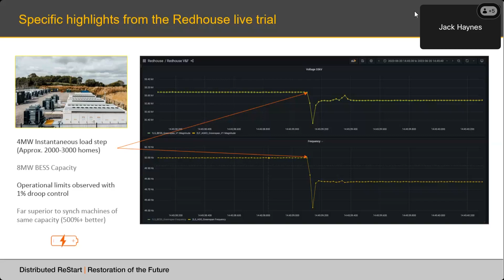Now, the BESS's capacity itself was only 8 megawatts, and we stepped 4 megawatts. If we had a larger load bank at our disposal, then we could have done larger steps. But from the analysis we're doing as part of the report, which will be published towards the beginning of October, it's apparent that the true block load capability of the BESS is probably tending towards its full capacity, which when compared to a synchronous machine is considerably better. You'd expect to get maybe about 20% block load pickup capability from a synchronous machine, whereas here we've demonstrated that you can get at least 50% out of the BESS, but in reality it's probably closer to its full capacity.